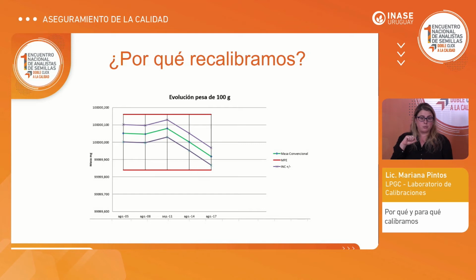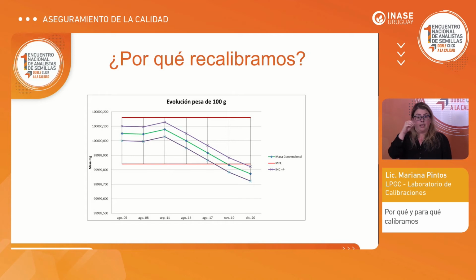This is the weight. The green line is the conventional value. The red is the limits that are allowed, and the purple is the uncertainty. So there is a moment when it's important that the weight is dropping. With the calibration, we can see a trend that the tolerance is going away. We are coming out of the tolerance. Maybe we can use the equipment for something else, or we correct the measurement and we change the ranges. And this is what calibration and recalibration is useful for.